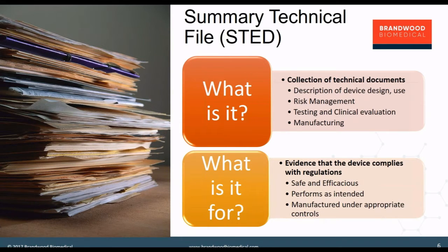That's essentially a collection of technical documents that will describe the device, its intended use, and contain some information about the risk management process that was followed, such as your risk analysis that have been used as part of your product development cycle, the test data that relates to this device, as well as the clinical evidence. In addition to that, there will be some information about your manufacturing plans, and again, we'll review in some more detail at a later stage what the content of that technical file is.